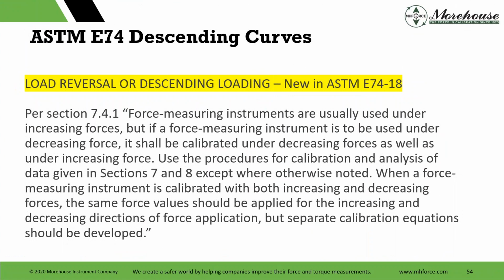And not to mention, ASTM E74 section 7.41 deals with it, and it says force measuring instruments are usually used under increasing forces, but if a force measuring instrument is to be used under decreasing force, it shall be calibrated under decreasing forces as well as under increasing force. Use the procedures for calibration and analysis of data given in sections 7 and 8, except when otherwise noted. When a force measuring instrument is calibrated with both increasing and decreasing forces, the same force values should be applied for the increasing and decreasing directions of the force application, but separate calibrations should be developed.